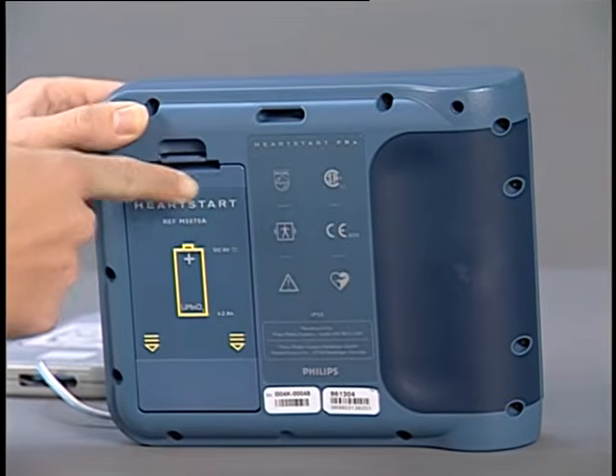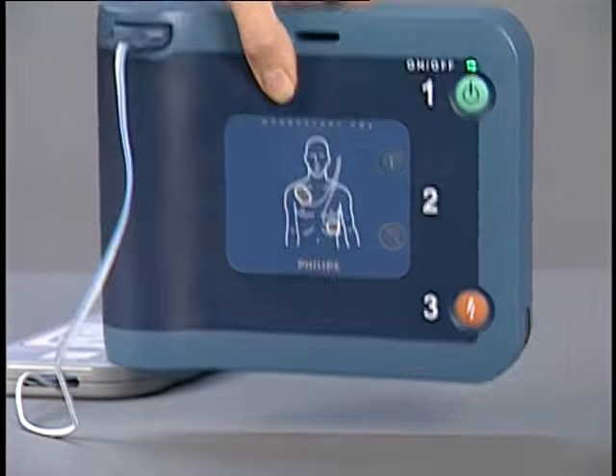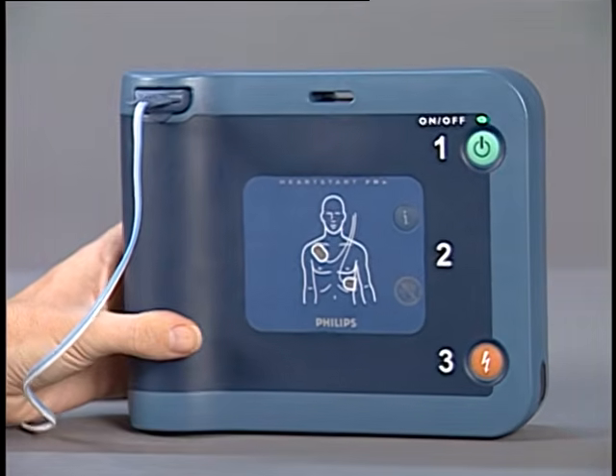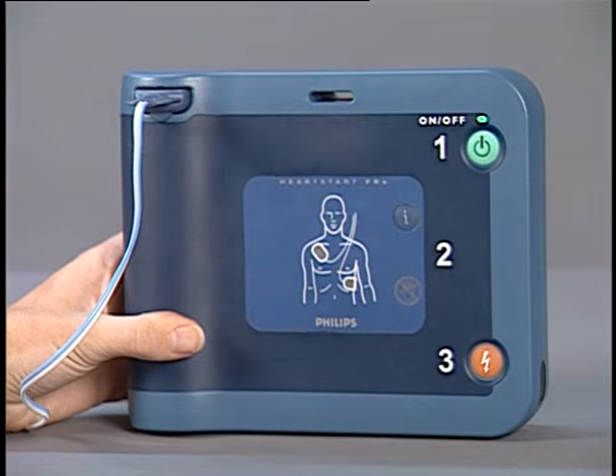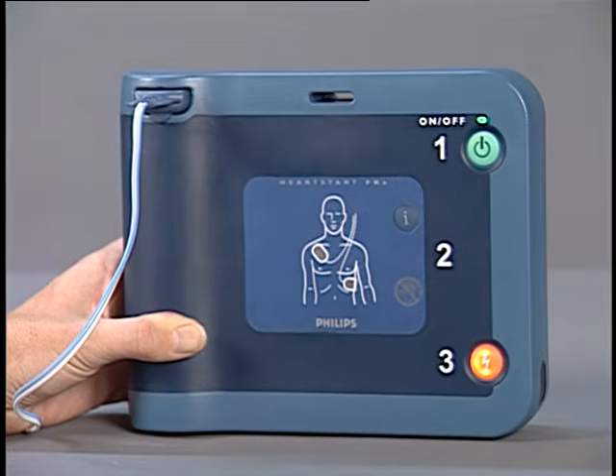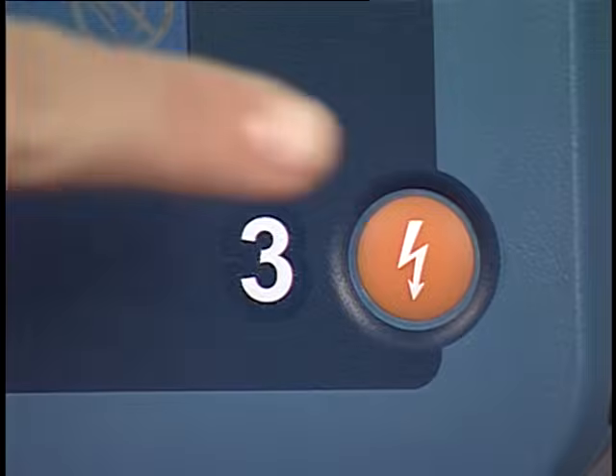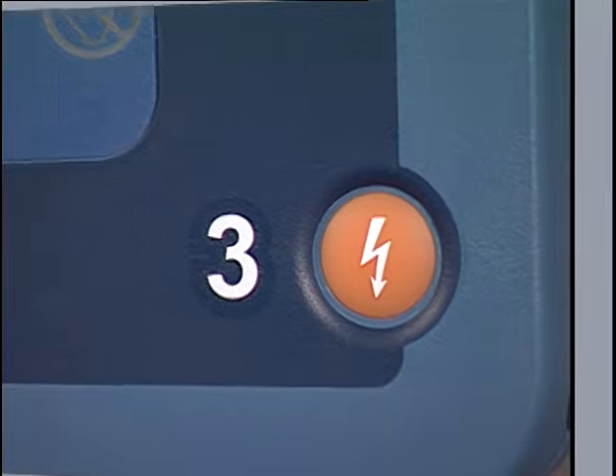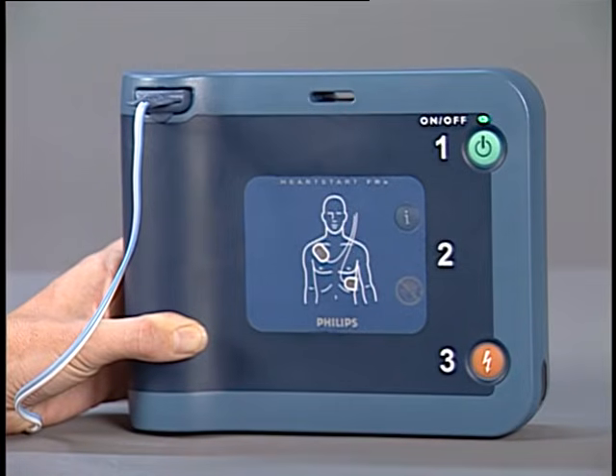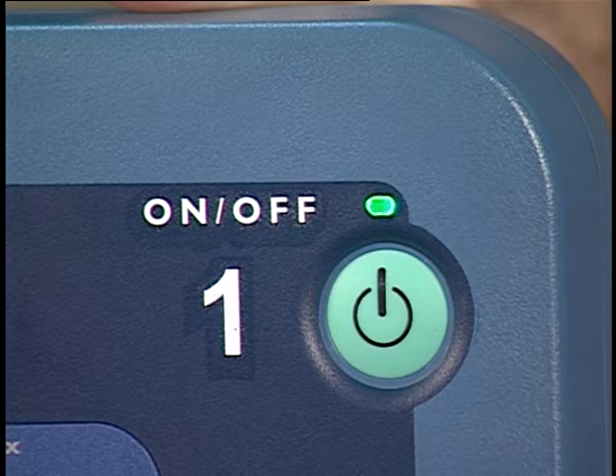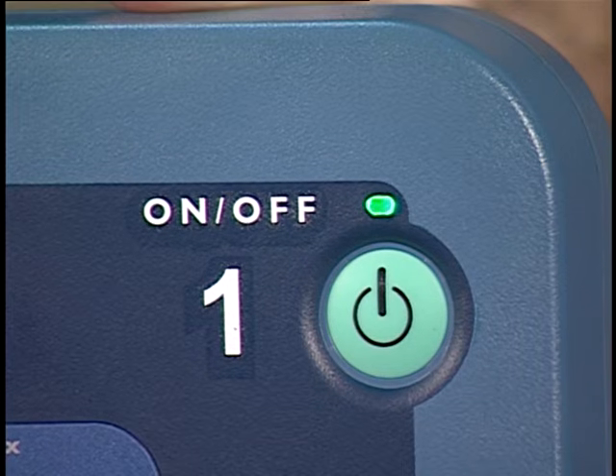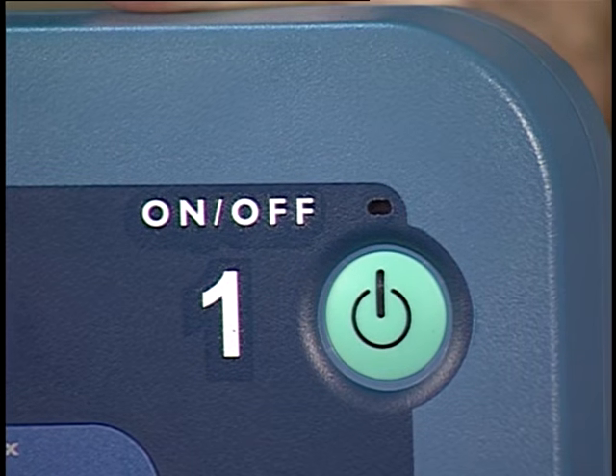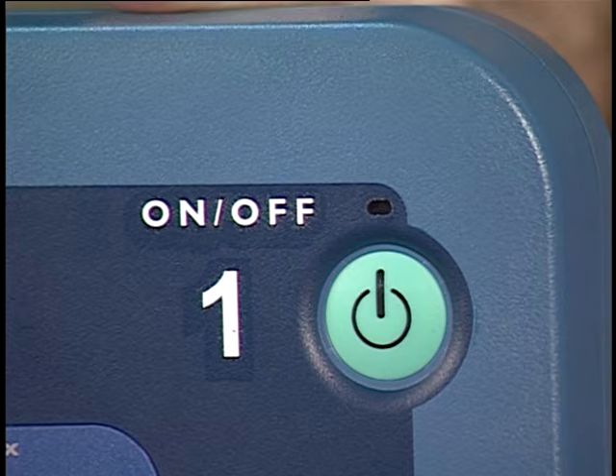As soon as the battery is installed, the FRx will run a battery insertion test. Beginning self-test. If this is an emergency, press the green on-off button. Be sure to let the test run and follow the voice instructions for pressing buttons when directed. The test takes just over a minute to complete. When the test is over, the FRx will report the results, then turn off and go into standby mode. The blinking green ready light shows the defibrillator is ready for use.